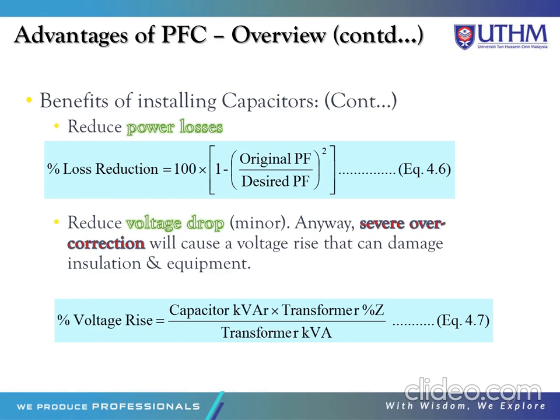Next, it can reduce voltage drop. However, severe overcorrection will cause damaged insulation and equipment. This is the formula to calculate the percentage of voltage rise: the capacitor value times the transformer percentage Z, divided by the kVA of the transformer.